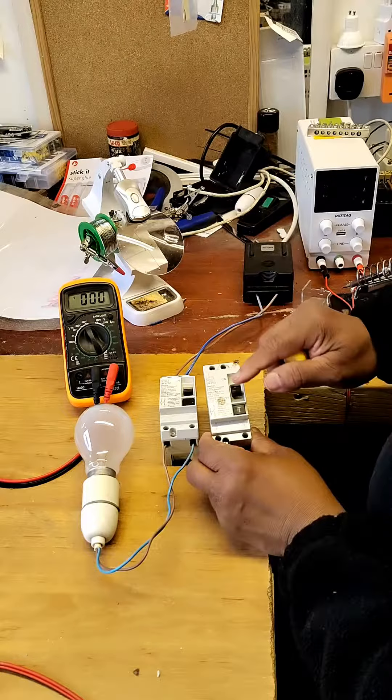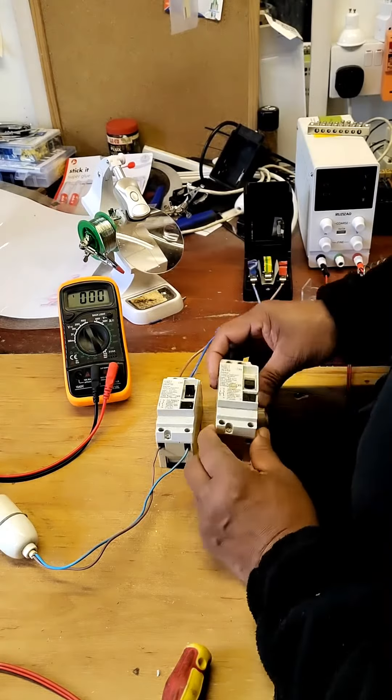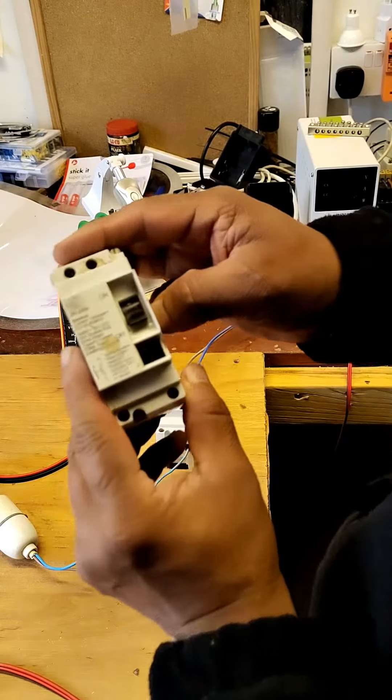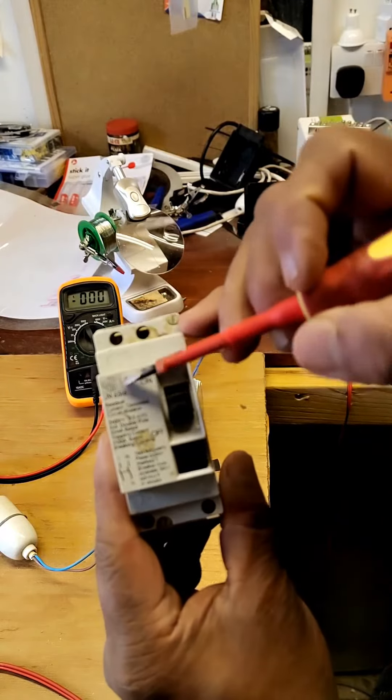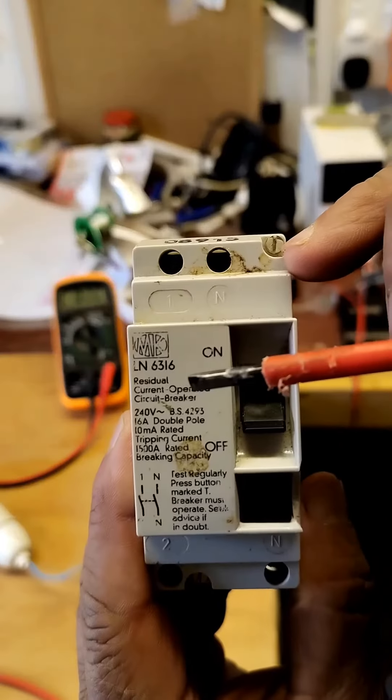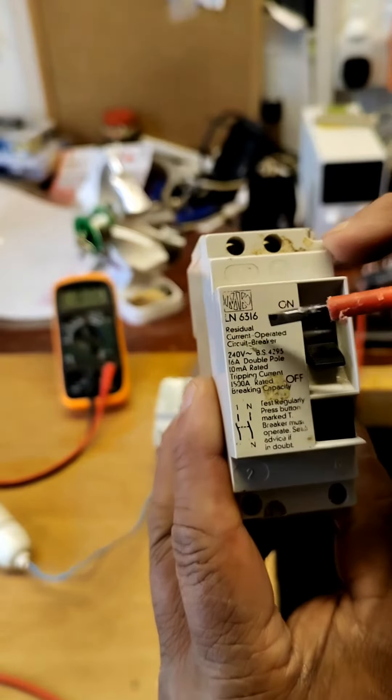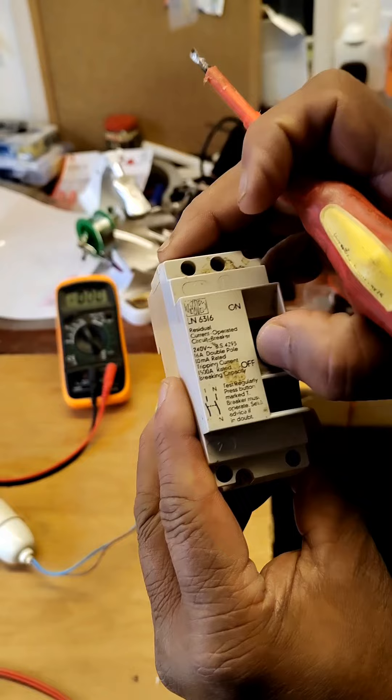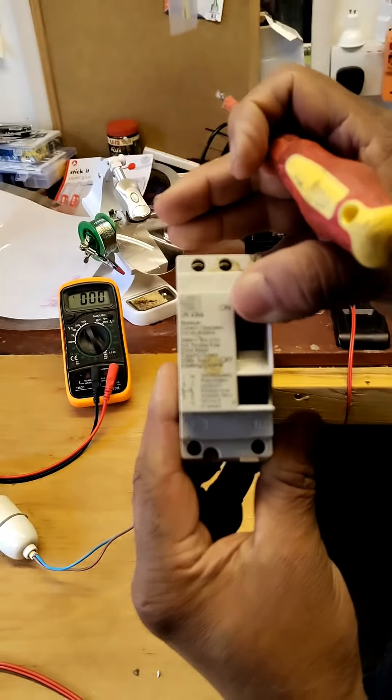This one is actually not working properly. So this is a 30 milliamp leakage current device. Once there is 30 milliamps of leakage, it trips out. It's supposed to be. So this is not working as you can see.